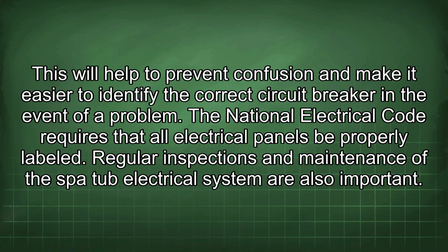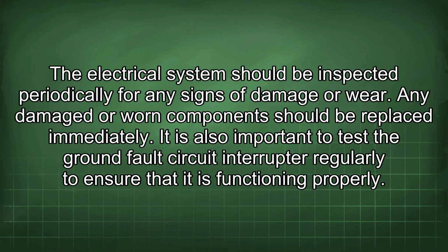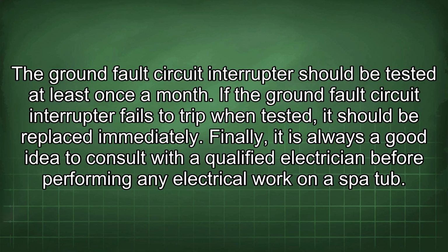Regular inspections and maintenance of the spa tub electrical system are also important. The electrical system should be inspected periodically for any signs of damage or wear. Any damaged or worn component should be replaced immediately. It is also important to test the ground fault circuit interrupter regularly to ensure that it is functioning properly. The ground fault circuit interrupter should be tested at least once a month. If the ground fault circuit interrupter fails to trip when tested, it should be replaced immediately.